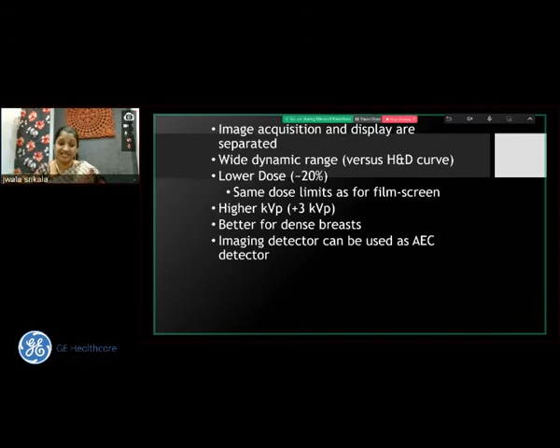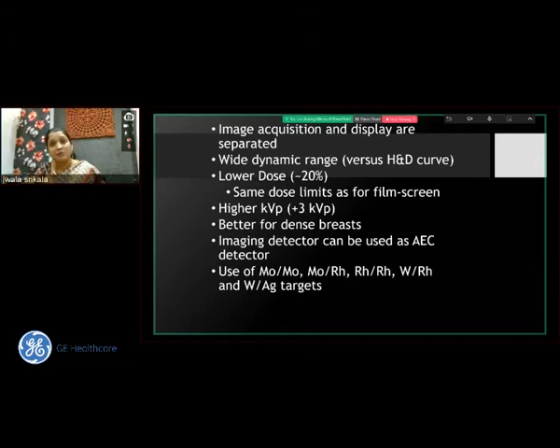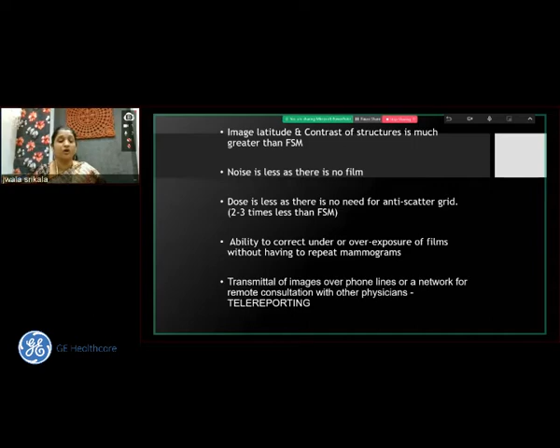It was doing better than film screen mammography for dense breast, and the image detector was the automatic exposure control detector also, and it gave us a little bit of leeway regarding the use of molybdenum and multiple materials as the filament and the filter materials. Image latitude and contrast of structures is much better than film screen mammography. Noise is less, dose is less, as there's no need for an anti-scatter grid, and there's the ability to correct under or overexposure of films without having to repeat them. And the best part is to be able to transmit these images across the globe for opinion, for presentations, or for archiving or for telereporting.